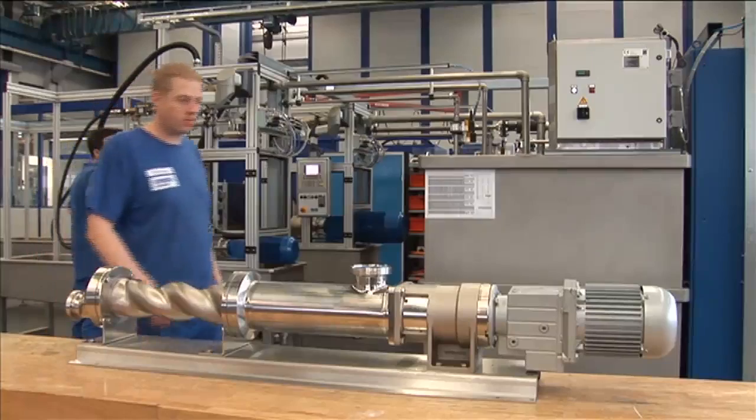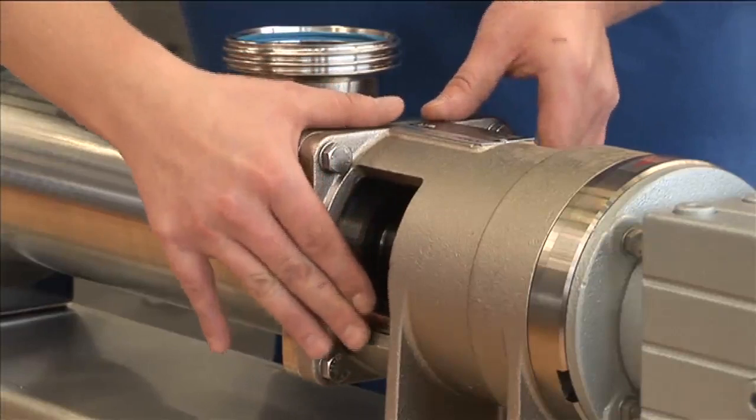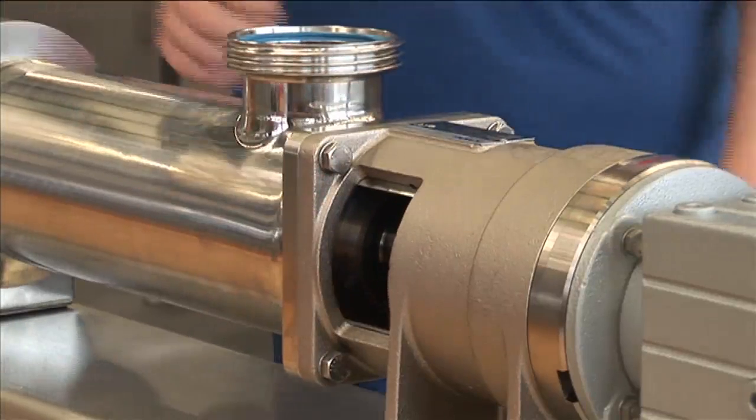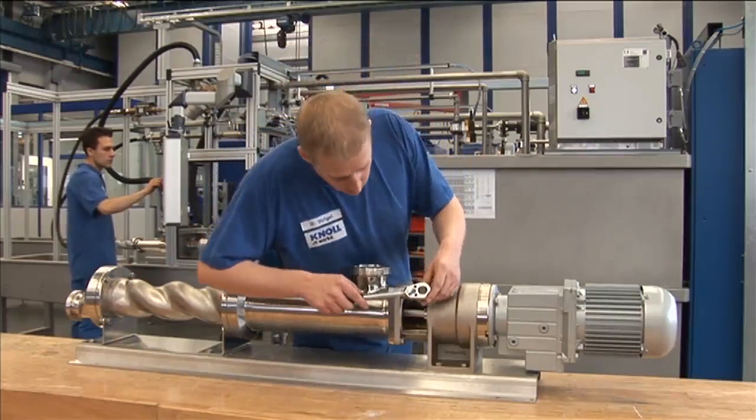The service technician must detach the rotating unit and the interface between the bearing block and suction housing through the service window to change the main shaft seal.